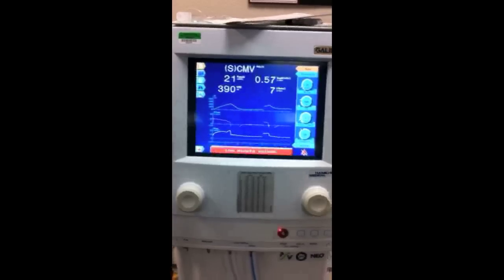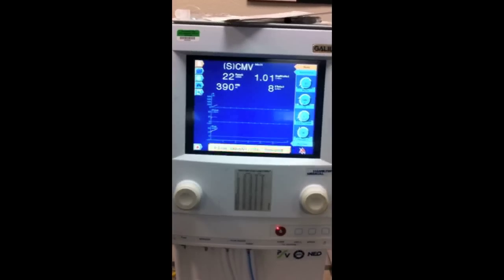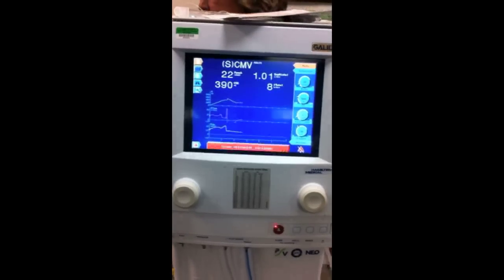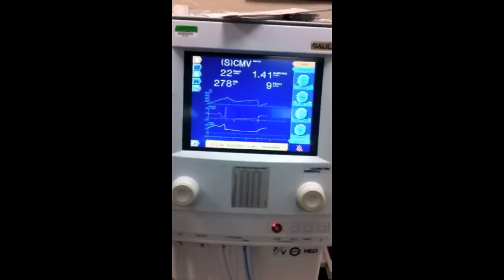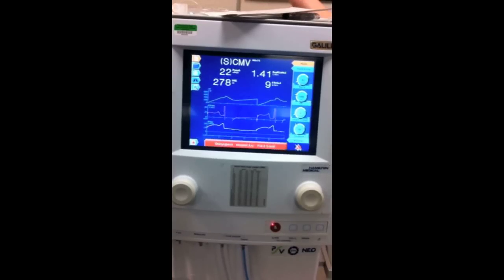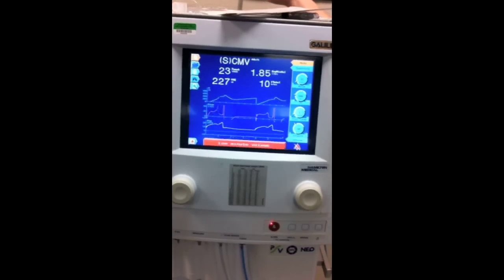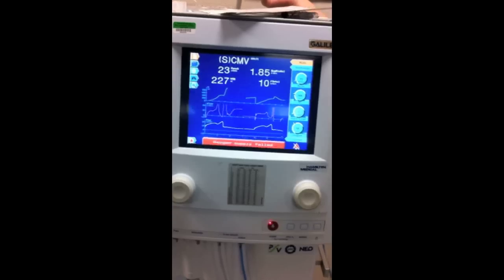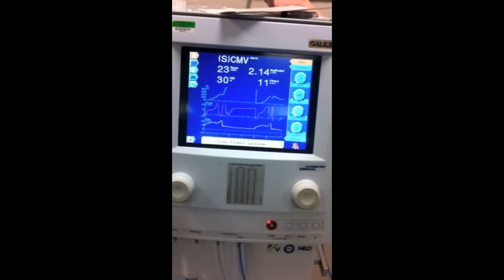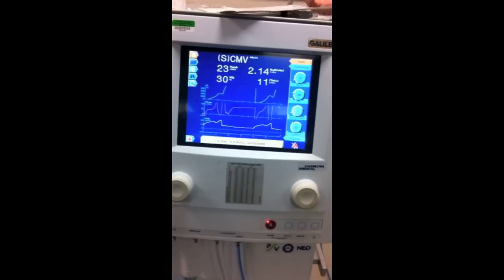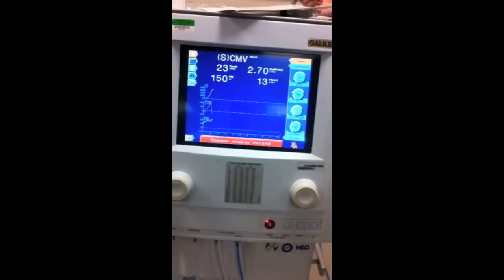And then it's going to tell us to unhook the oxygen. So when we do that, we'll get an alarm that tells us that the oxygen supply failed. The other ventilators ran you through an actual step through the screen. This one is just a manual way to do it, and it takes a minute, but in a minute we'll get that the oxygen supply failed. And so you'll just keep going through that.